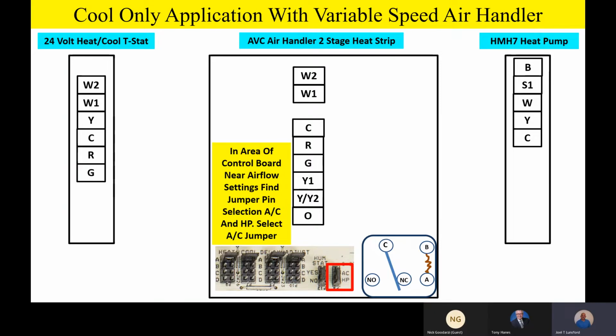So two things. Number one, we're just going to have the single relay. This would be like the 001 kit or just a single pole double throw relay that you mount in there, and a bi-flow filter dryer. But go on the control board of the variable speed air handler, where the airflow settings are, the heat, cool, delay, and so on settings. You're going to find a little jumper that says AC or heat pump. Move that jumper to AC. Now, in a straight cool application, when you move that jumper to AC on the air handler, it's going to ignore the O terminal.